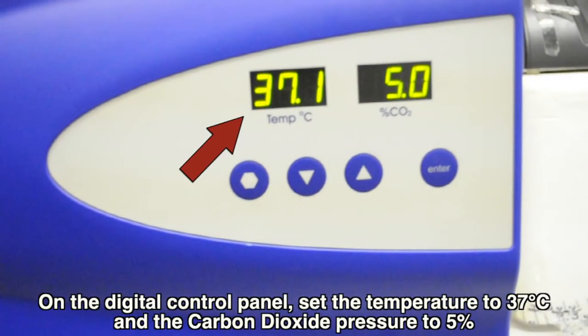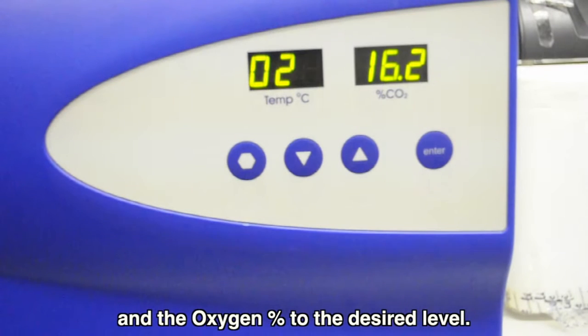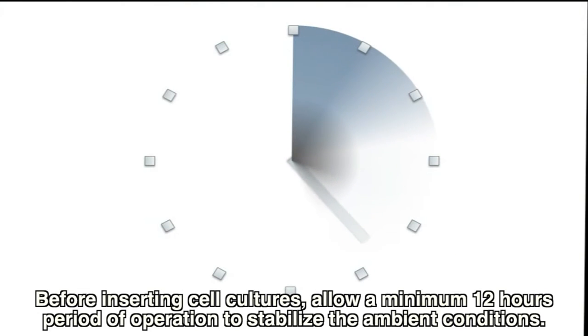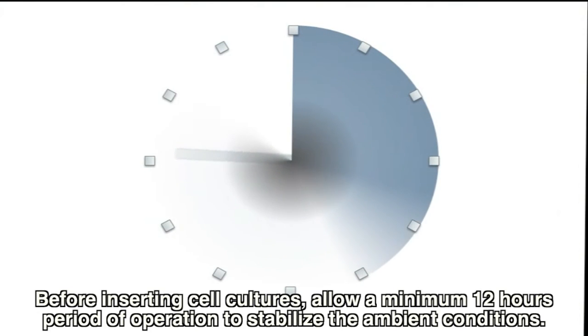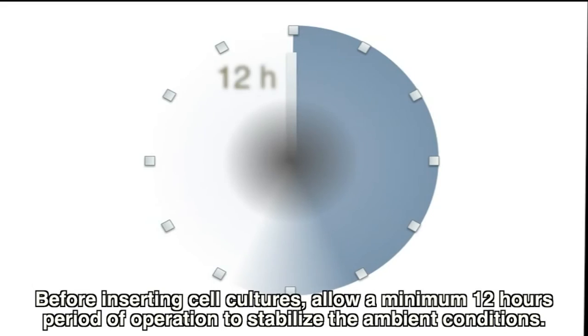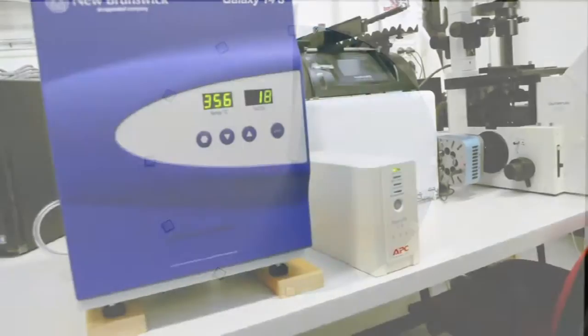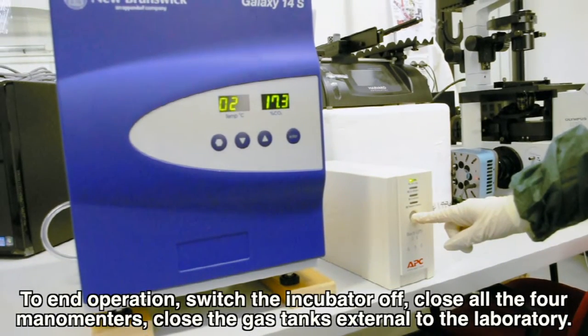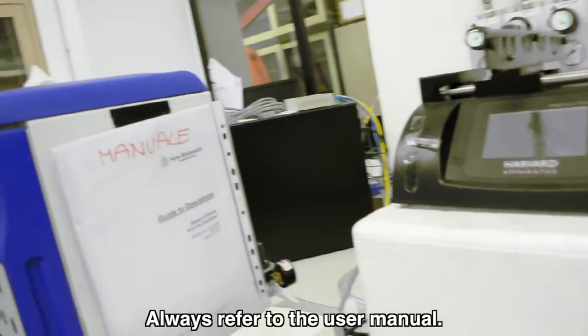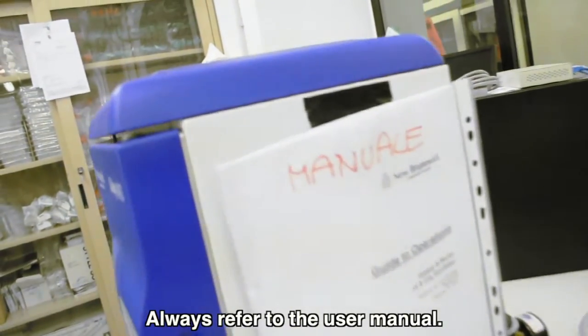On the digital control panel, set the temperature to 37 degrees and the carbon dioxide pressure to 5% and the oxygen percentage to the desired level. Before inserting cell cultures, allow a minimum 12 hours period of operation to stabilize the ambient conditions. To end operations, switch the incubator off, close all the 4 manometers, close the gas tanks external to the laboratory. Always refer to the user manual.